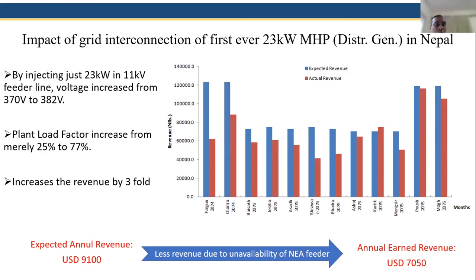This is mainly because of the unavailability of the NEA, meaning the utility feeder line. Whenever there is no grid, you cannot sell electricity into the grid or into the community. For selling electricity, you must have a grid available to connect your micro hydro system. This was mainly due to the 11 kV outage of the feeder line. Our experience shows that we should not go into 400 volt interconnection of micro hydro systems. Whenever you connect at 400 volt, there will be more outages and you will lose more revenue, as the availability of the 400 volt line is lesser than the availability of the 11 kV line.